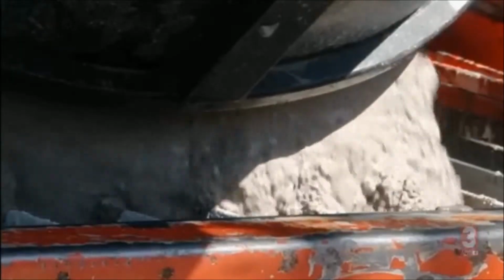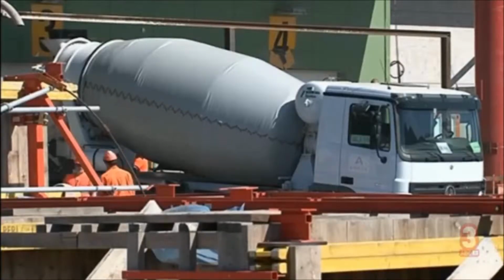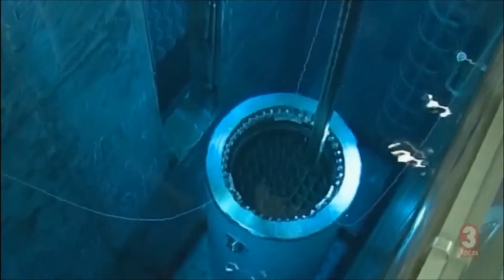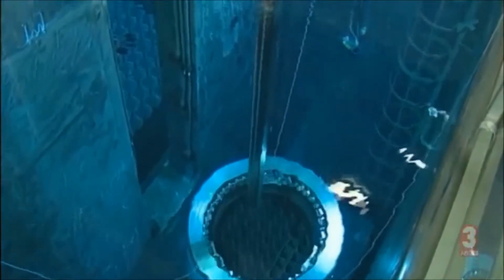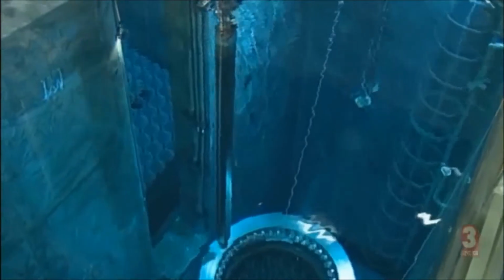Post-Chernobyl meltdown, the plant in Finland has added some new safety features. You take into account the very, very low probability of having the worst possible accident. And the worst possible accident is you melt down the totality of your core. If that happens, and if this kind of molten lava is able to get out of the big pressure vessel where it is contained, then we have a kind of ashtray, if you want, where this molten lava will be spread and then solidified in situ, where it is.